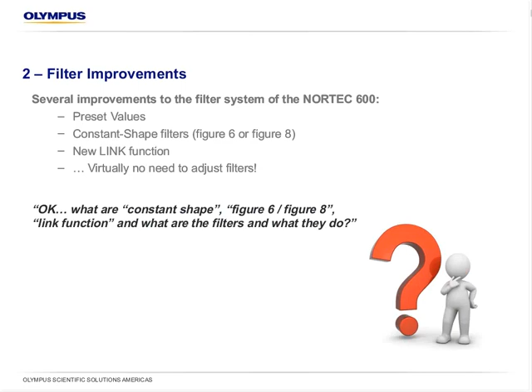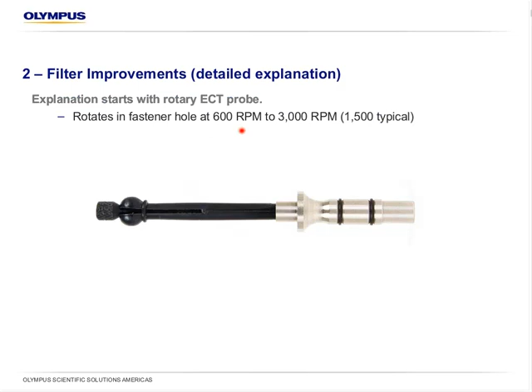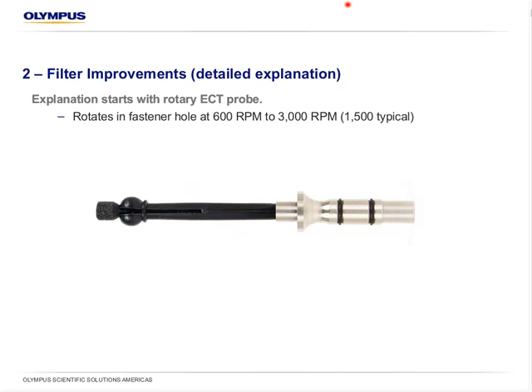The explanation starts with the probe. So we have to know a bit of the probe construction in order to understand the rest. Without going into too much detail, really, that probe is basically rotating in a fastener hole, whether it's a plastic probe, it's expandable, it's stainless, or stainless expandable. They all do the same job pretty much. They rotate from 600 RPM to 3,000, 1,500 RPM being a very common speed where POD, or probability of detection, studies are made.